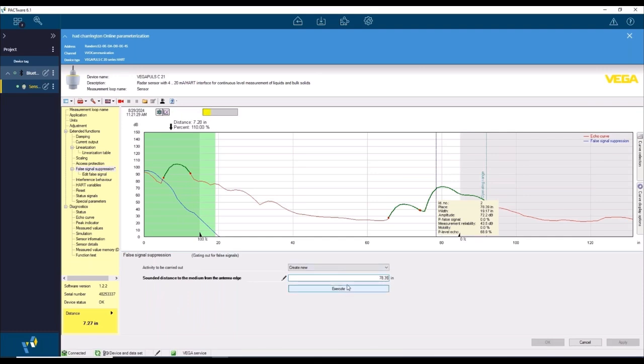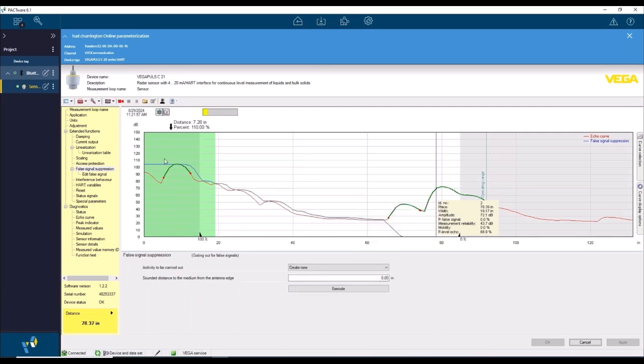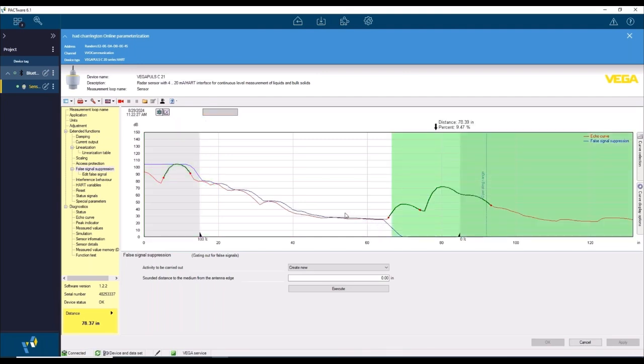And then note that whenever you change something in this DTM window, you're going to see that little pencil mark. So note that if you see pencil marks, don't forget to hit apply or execute to write the data. So here I'm going to do execute. Okay, now you can see that the blue line, which is called our false signal suppression line, has now advanced itself further downstream, and now note that my gauge is now reading correctly. The black arrow has jumped down to the actual level, and the actual level currently is at 9%.